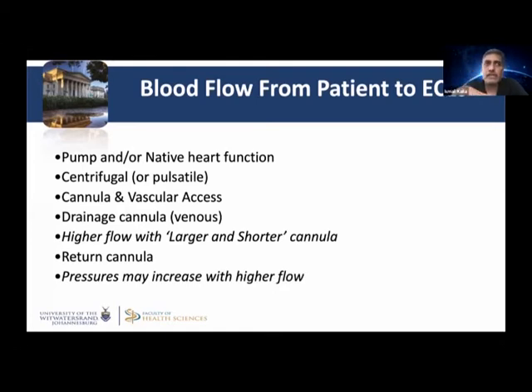So the conceptualization of this particular form of therapy is completely different in terms of the flow principles and the flow rates that we achieve in transitioning from ECLS versus CRRT. The second one is that the motors or the pumps that we use are completely different. We don't use roller pumps. We use Levitronix pumps or centrifugal pumps, where we can generate a significant amount of flow rates without traumatizing the red blood cells. The third issue is cannula line access, and I'm sure you're all familiar with cannula line access.